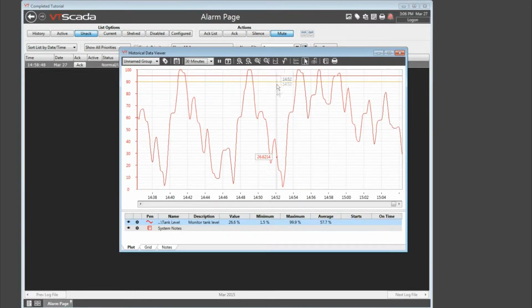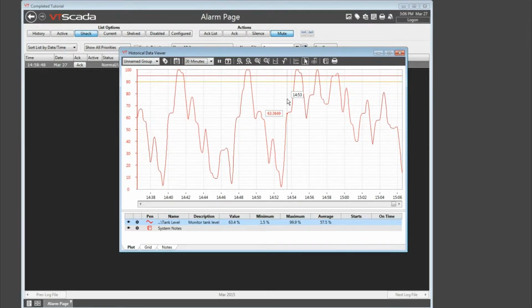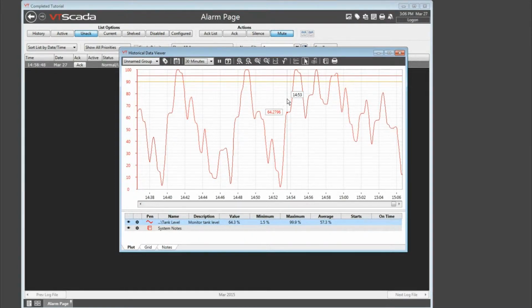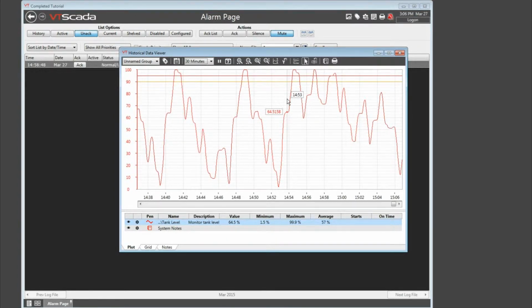As you move the cursor back and forth, the value under the line will be shown. Now be careful about that. Depending on the time span shown, a pixel might be between two logged values and thus show an interpolated value. Or each pixel might represent 20 or 50 logged values and therefore be an average. Unless the time span is a perfect match for the logging rate, with every pixel corresponding to a distinct logged value, the numbers shown do not and cannot represent the actual logged values.